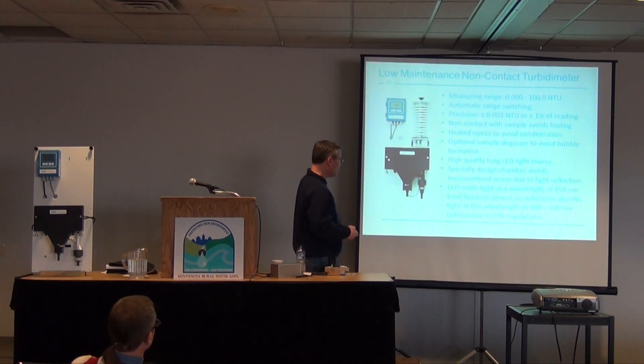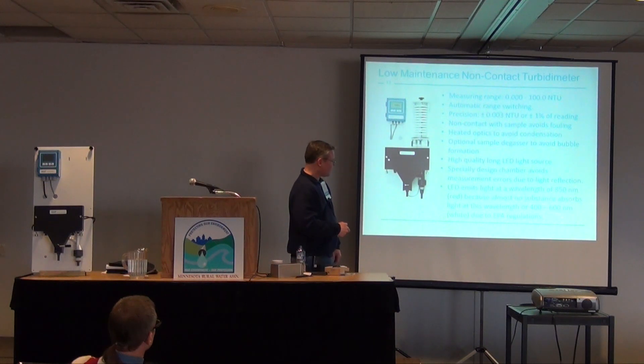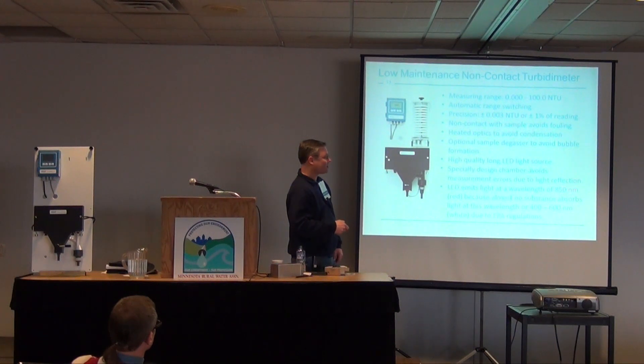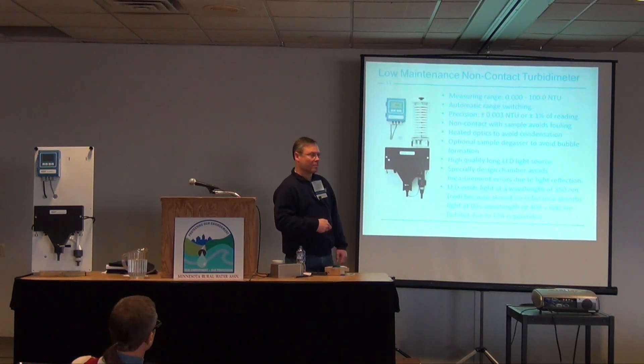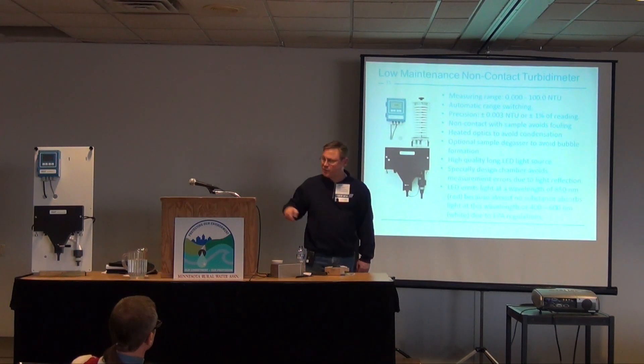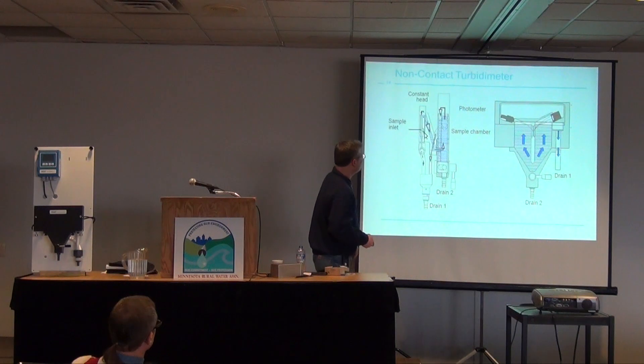We have two versions of this instrument: one at 850 nanometers and a white LED version. When Swan submitted the instrument to the EPA, they approved it and approved the method. Our original design used the 850nm wavelength. But after we started production when Swan USA launched in 2010, the EPA called our president Chris Treyer and asked us to redesign to a white LED, because EPA Method 180.1 calls for a white tungsten light source. So we actually have two designs on this instrument because of the EPA.